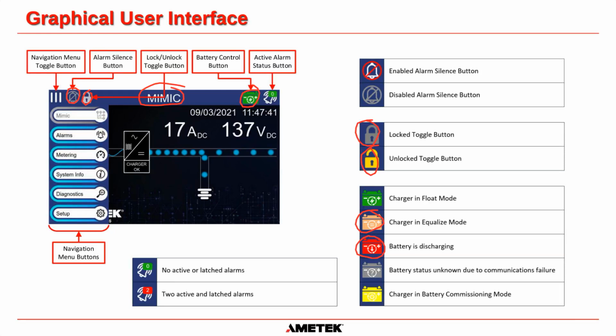If we have a communication failure, that battery will turn gray. One of our last options is a battery commissioning mode, which sets the voltage higher than even the equalized voltage to commission a brand new battery. Sometimes battery manufacturers require this. It'll show you if it's in that commissioning mode when the battery is yellow. That's especially true for NiCad batteries.